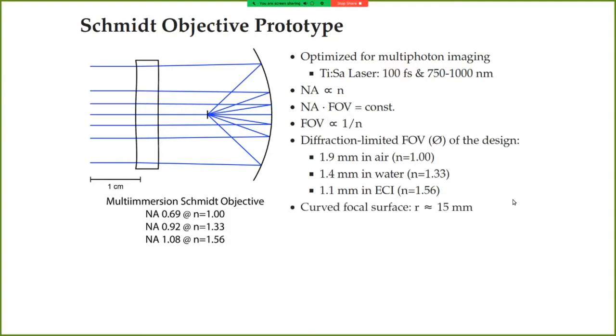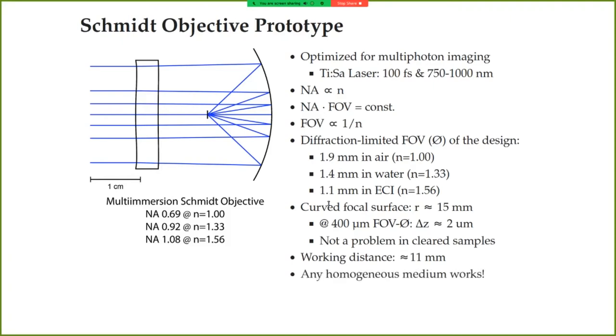These focal surfaces curve with a radius of roughly 15 millimeters. This means in practical terms that for a field of view that has 400 micron diameter, zones that are at the very edge of the field of view will have a focal shift of 2 micron compared to zones at the center of the field of view. And this is usually not a problem in cleared samples. The working distance is approximately 11 millimeters. Of course, in this design, we can discuss a little bit how one defines working distance. In this case, it's just a mechanical distance we can move before we hit the mirror with a larger extended sample. And as I pointed out, any homogeneous medium works. And obviously, the sample partially blocks the optical path, both in the excitation and detection path, but this is totally acceptable up to sample sizes of six by six millimeters.